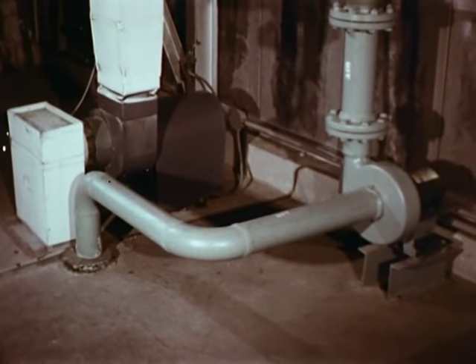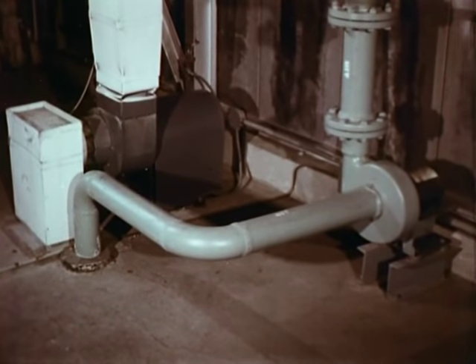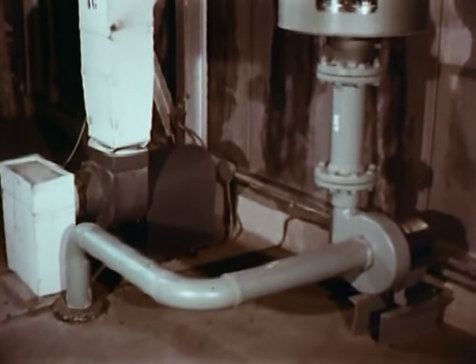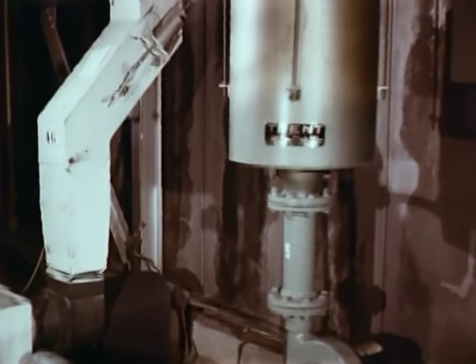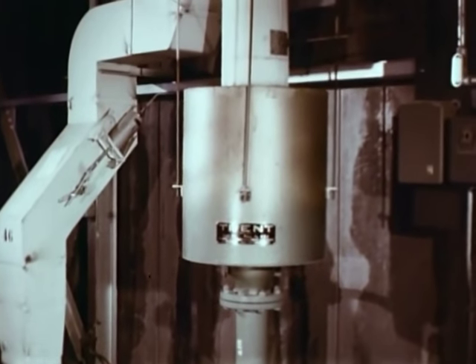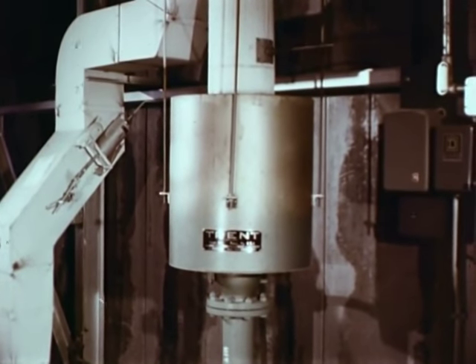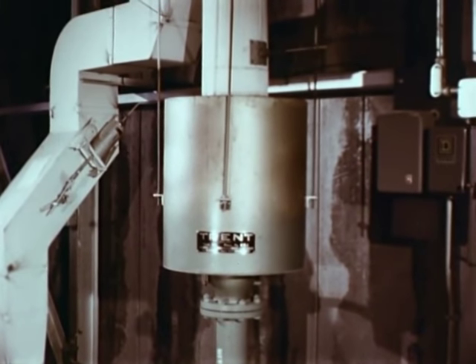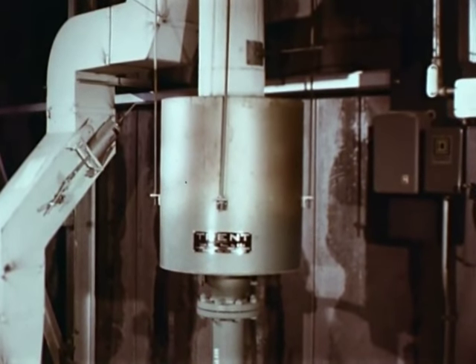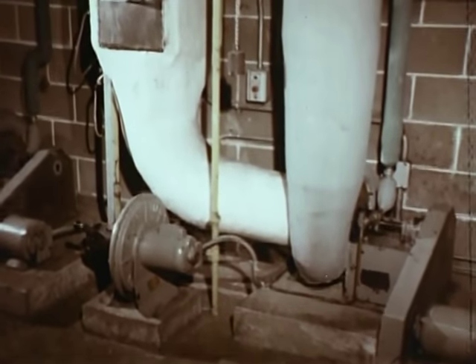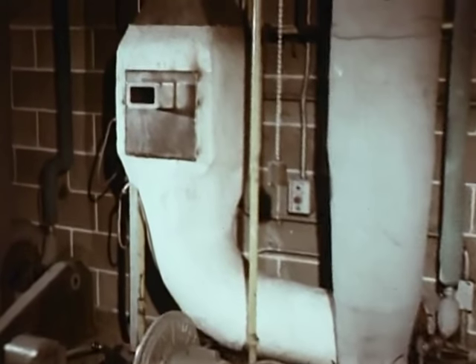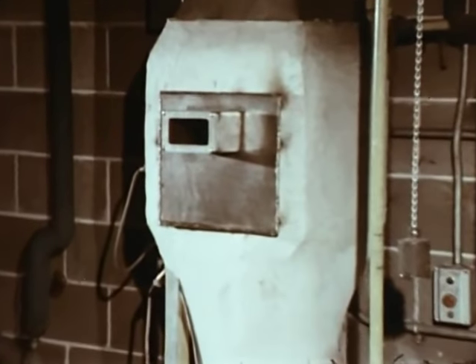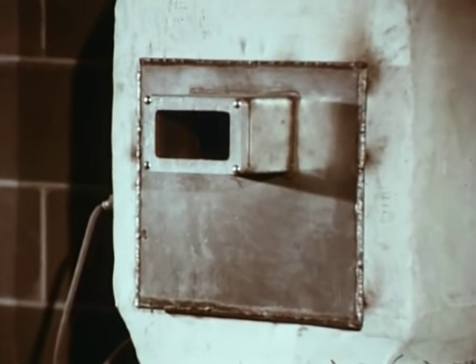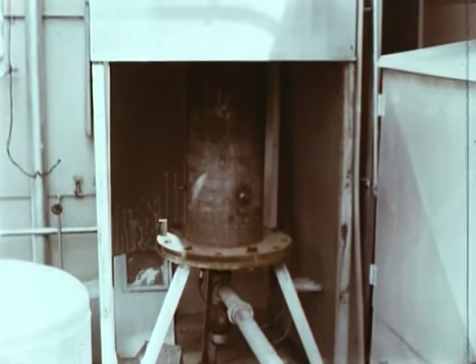Exhaust air from aerosol chambers and other high-hazard equipment should pass through welded pipelines to an incinerator. Electrically operated units are both practical and efficient for quantities of up to 100 cubic feet a minute. This unit and the ones that follow should be preceded by a microbial filter as a fail-safe device. For larger volumes of air, gas or oil-fired incinerators may be used. With this oil-fired unit, a tall stack serves to discharge the air at a substantial distance above the building.